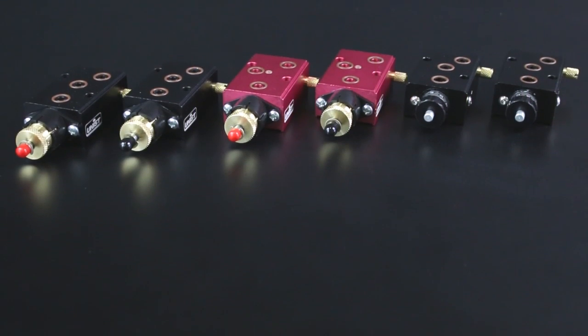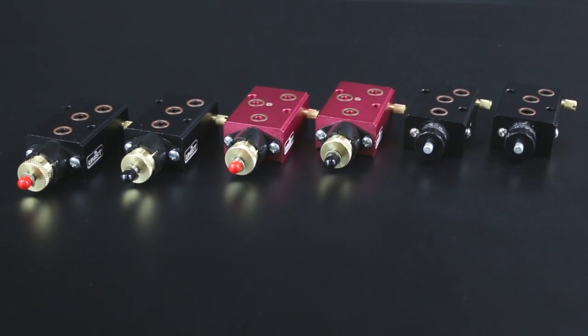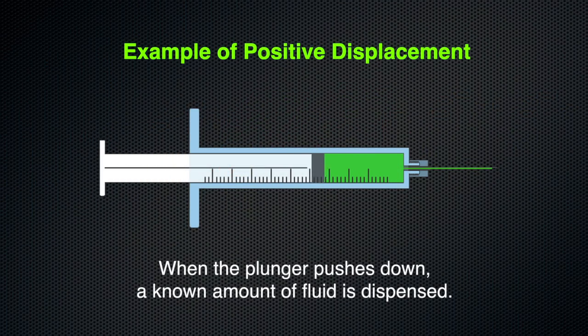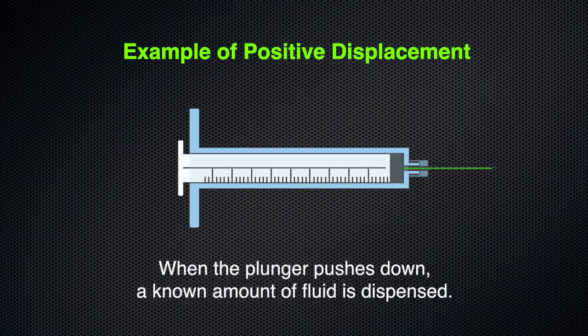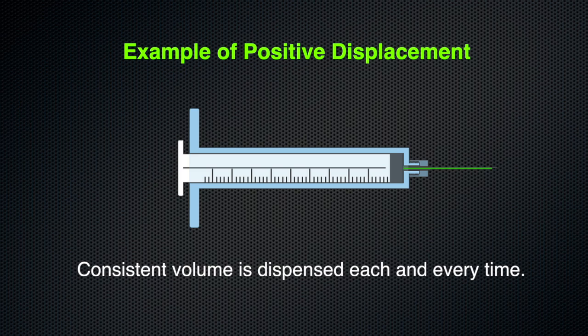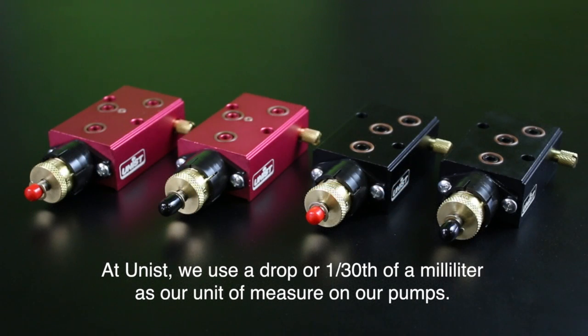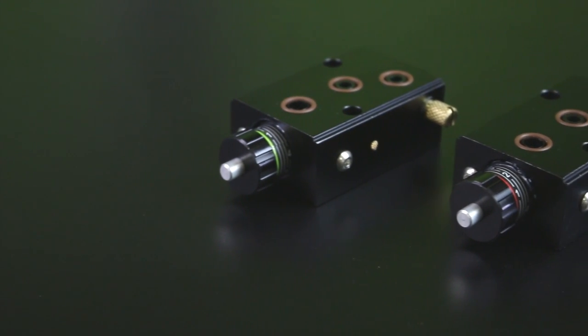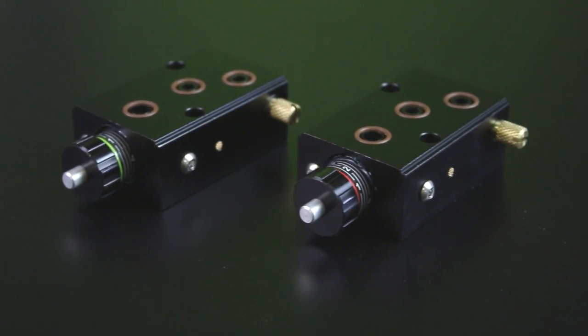Larry brought several examples of Unist positive displacement pumps used in their systems. For those not familiar, positive displacement works like a syringe: when the plunger goes down, a known amount of fluid is dispensed. This is more accurate and repeatable than other fluid metering methods because a consistent volume is dispensed each time. At Unist, a drop — or 1/30th of a milliliter — is the unit of measure. Pumps are rated for maximum output per stroke but can be adjusted down to fractions of a drop.